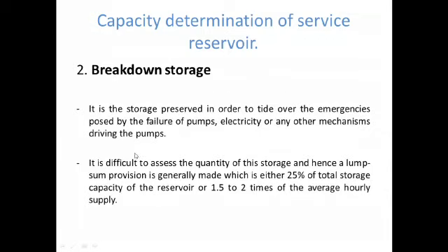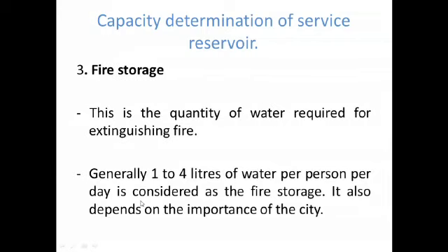And the next one is the breakdown storage, that is due to failure of pumps or electricity or any other mechanisms driving the pumps. This is taken into account, and it is difficult to assess the quantity of this storage, and hence a lump sum provision is generally made, which is either 25% of total storage capacity of the reservoir or 1.5 to 2 times of the average hourly supply.